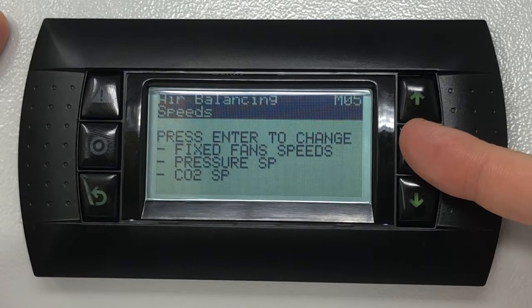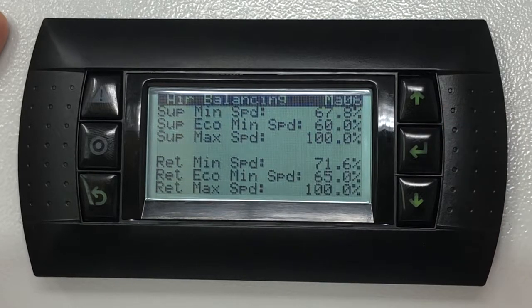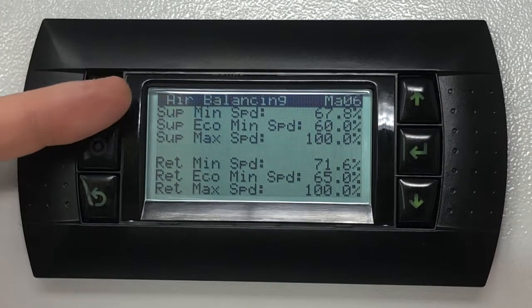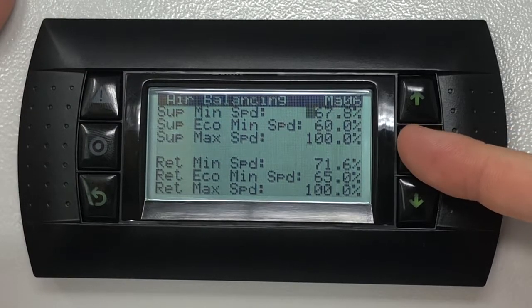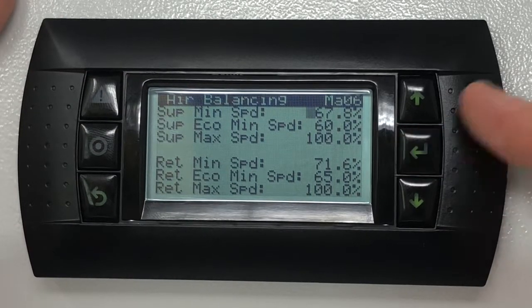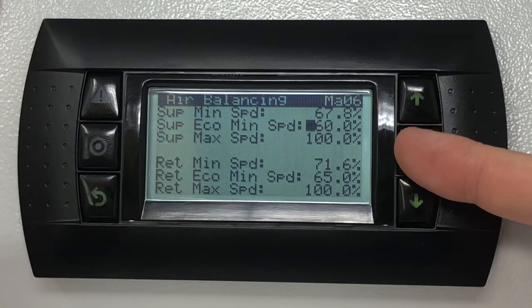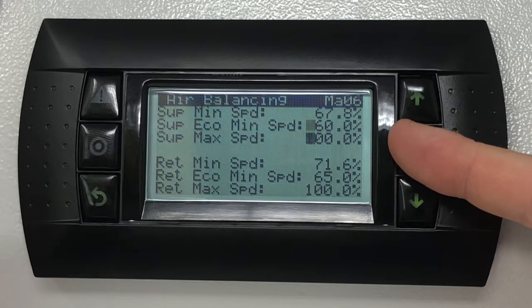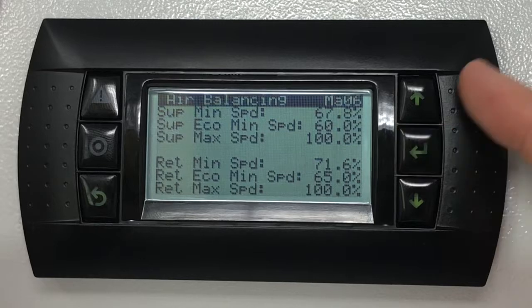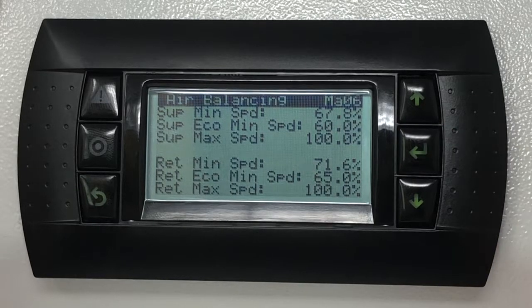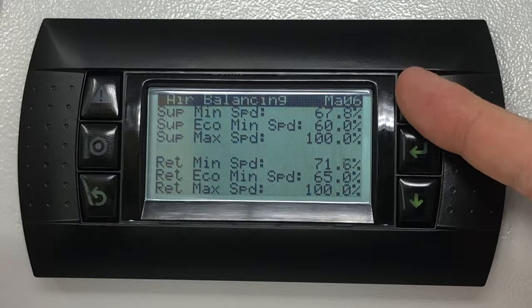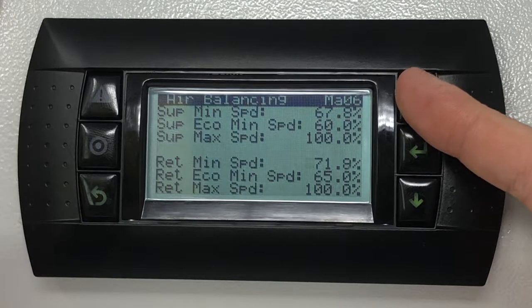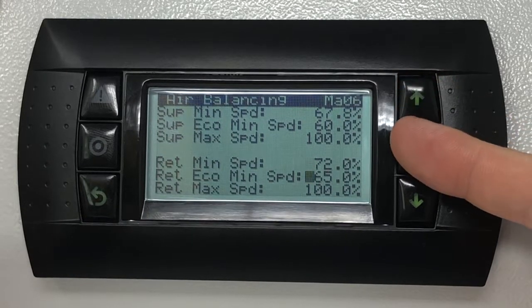Press the enter key and you'll notice that the cursor will pulse on the top left of the screen. Press the enter key again and this will drop the cursor onto the field you will need to change. By pressing the enter key the cursor will move to the next field in line. Once the speed you wish to change is highlighted, using the up and down keys change the value to the desired percentage and press the enter key to confirm.